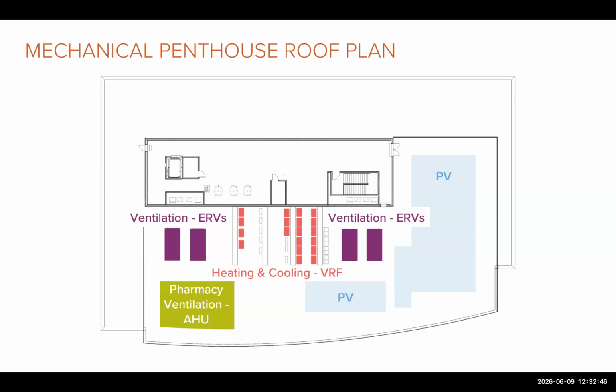So this is our roof plan showing our primary mechanical systems. You'll see we have shown in pink a centralized VRF system for our heating and cooling for the building. The purple is 4 centralized ERVs, and that's required for the ventilation for the building. This is different from what we often do for multifamily projects, where each unit might have its own dedicated heat pump and ERV instead of centralized systems that serve the whole building.